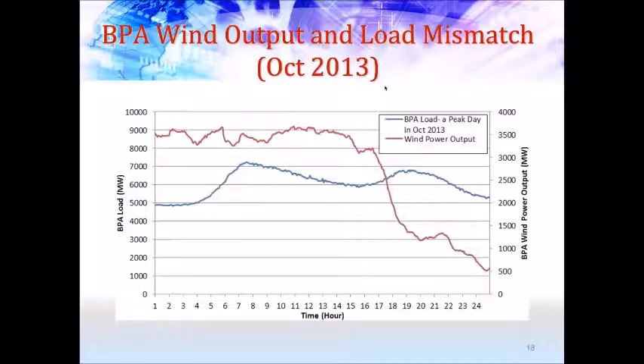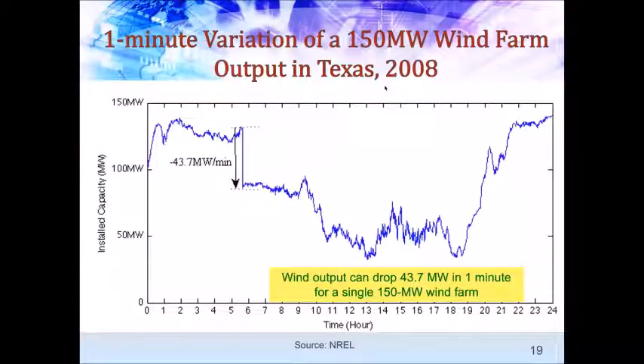That's the autumn data. Now, variations. This is data from a 150 megawatt wind farm in Texas. It's working quite well on a given day, about 140, 135 megawatts. Then suddenly about 6 a.m., the wind stops or slows down. Your load is only 100, the supply is about 90 megawatts. So from 140 it became 90, keeps dropping, goes as low as 40 megawatts, then picks up. If you don't take this into account, you'll have difficulty managing your load when the supply suddenly changes.